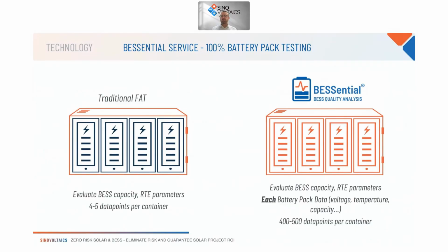If you are an asset owner, an IPP, or the buyer of that asset, you will have contractualized a certain amount of capacity with the supplier. This test basically shows how much capacity is available in that given asset. Typically in FATs, 10% of those assets are checked for capacity. So if you have a 10 container project, one container is going to be sampled and then capacity or performance tested.